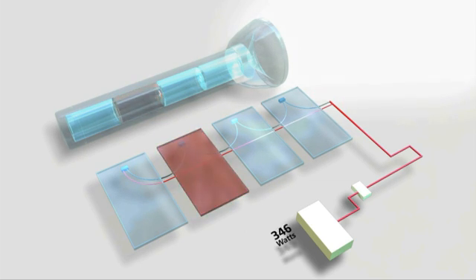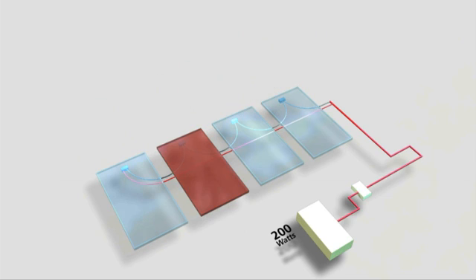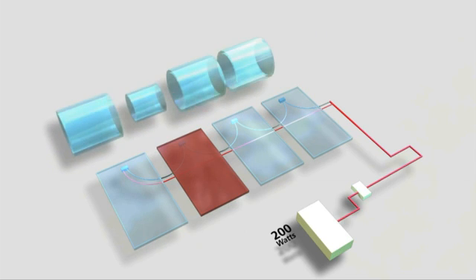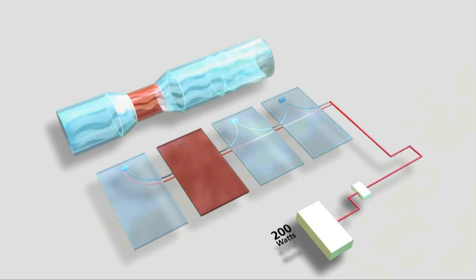when one module underperforms, it not only outputs less, it also drags down the other modules in the string. You can think of solar modules as pipes. Perfect modules have a larger pipe. Underperforming modules have a smaller pipe. When connected together, the small pipe constricts the flow of energy through the array and loses power by heating up the module. This can result in significant power losses and panel damage.